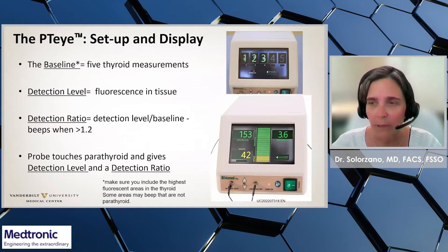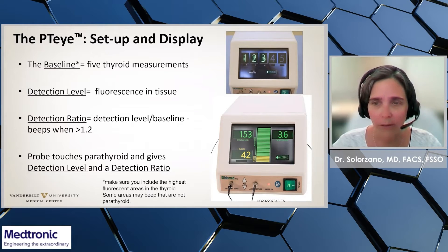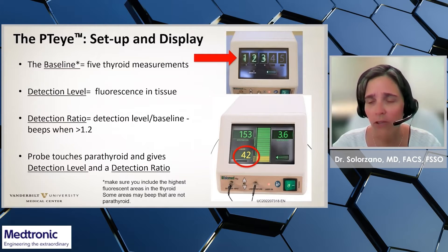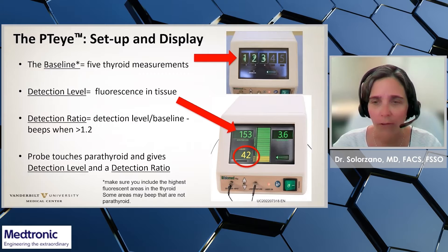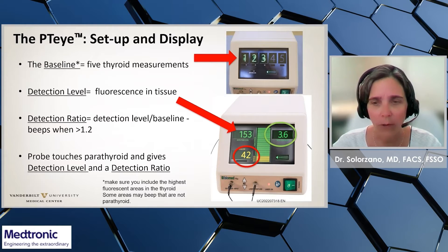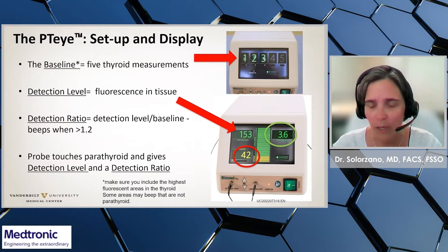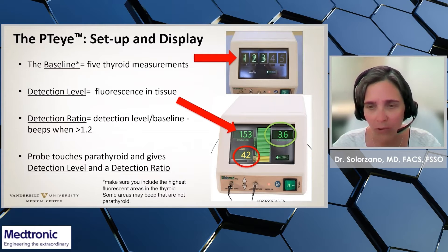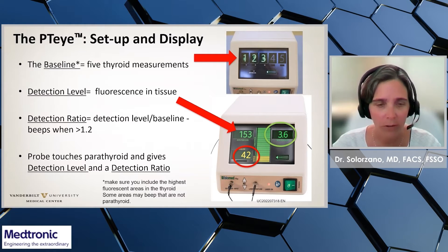Here is how to interpret the PTeye display. When you turn on the console, you will need to set the baseline by taking five thyroid measurements. When the probe touches tissue, it gives a detection level and a detection ratio. The threshold for parathyroid detection is set at 1.2 times the baseline, and the PTeye will beep. The example here shows a baseline of 42, a detection level of 153, making the ratio 3.6, consistent with parathyroid tissue.